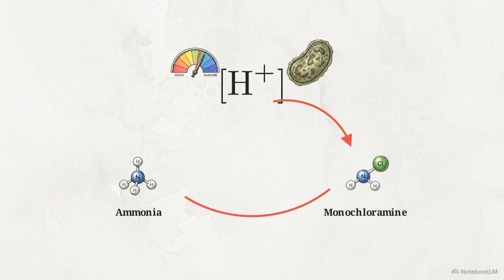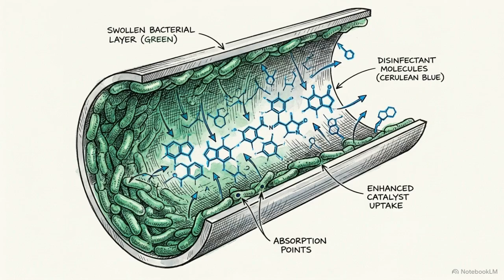This creates a thermodynamic feedback loop. The lowered pH accelerates further chloramine decay, which in turn releases even more ammonia. The primary disinfectant inadvertently acts as a biological catalyst, feeding the very biofilm it was designed to destroy. That localized drop in pH directly feeds into the second vulnerability and the direct mechanical cause of the DC water crisis: scale destabilization. Water systems rely on oxidation-reduction potential, or ORP.